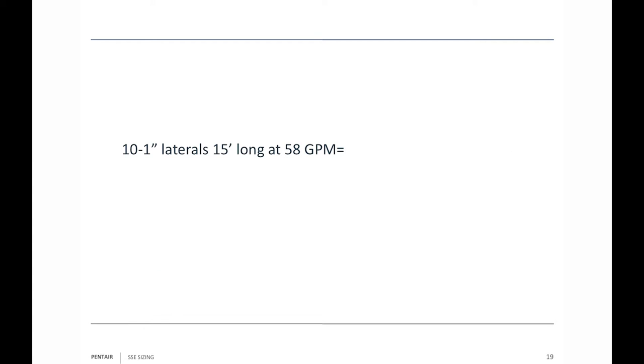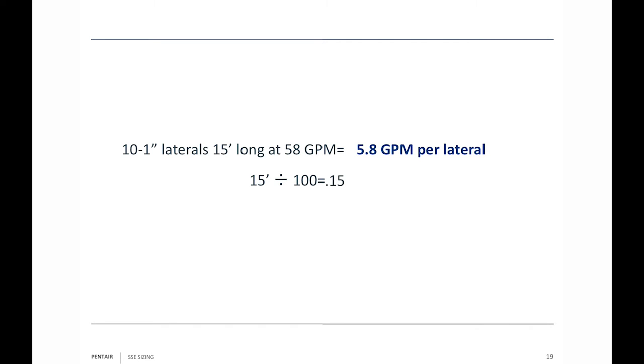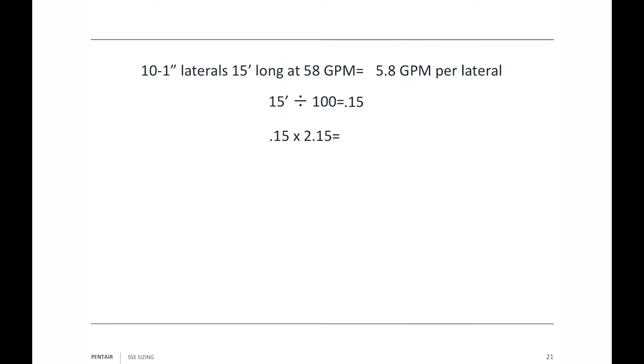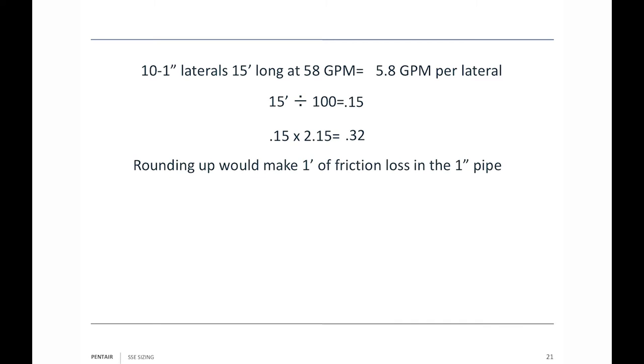For the 10 one-inch laterals, each 15 feet long, distributing 58 GPM total means 5.8 GPM per lateral. 15 feet divided by 100 gives 0.15 hundred-foot lengths of pipe. Looking at the friction loss chart at 6 GPM through one-inch pipe gives 2.15 feet per 100 feet. So 0.15 × 2.15 = 0.32, rounded up to 1 foot of friction loss in the one-inch pipe.